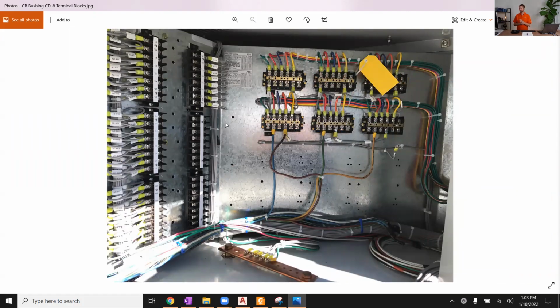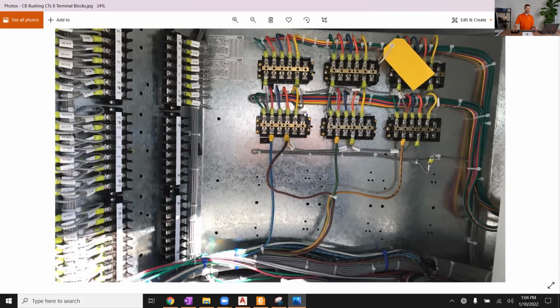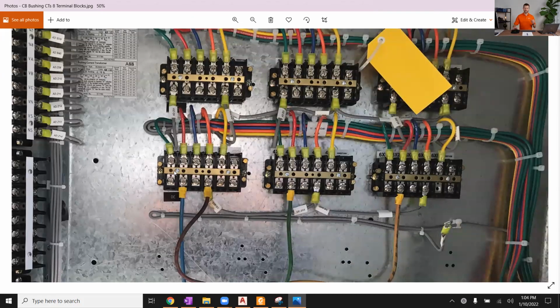Any other questions on, let's see, William asked a question. Do we ground the CT so they can be bypassed or shunted later using the test switches? You're correct. Kind of to that very shorting concept that I was just talking about with Sean. We're going to look at test switches and we're going to look at shorting test switches and shorting terminal blocks. And, if you're not using a CT, you should always come here and short them out in the breaker cabinet. If you're not wiring it to anywhere, you should have the full tap shorted out, either with shorting screws or maybe even with a jumper to do so. And the reason for that is you never want to have an open circuited CT. I do plan to talk about that later on a little more, but that's a dangerous, hazardous condition.